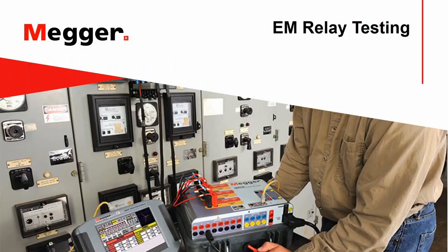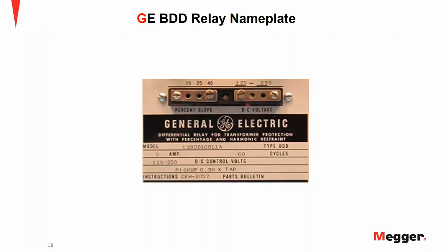And this is where we're going to start looking at the BDD relay that I have selected for this. In the BDD relay, we're looking for a few things. We want to make sure that once we do our testing, we get all the proper nameplate information. We want to make sure that we have the right instruction leaflet, the right model number of the relay that we're actually testing, and that we're on the right relay type.